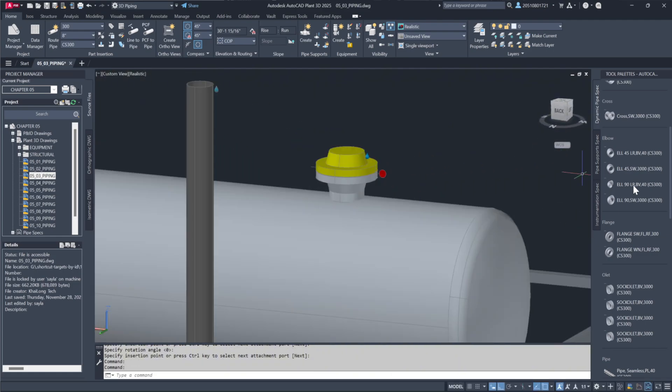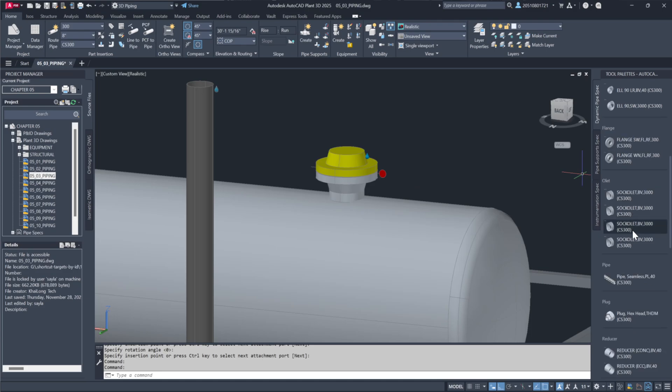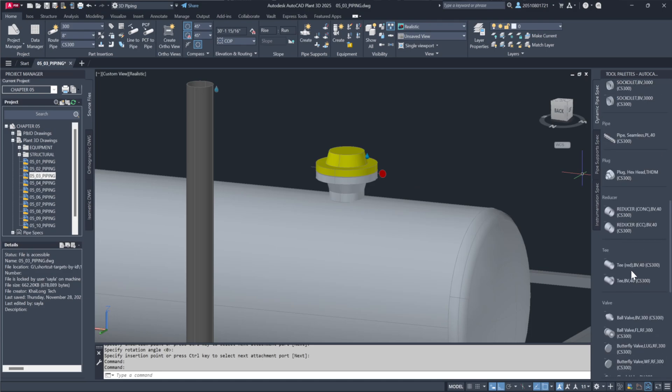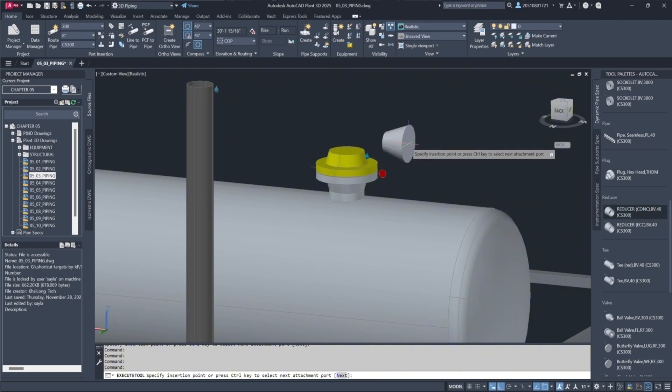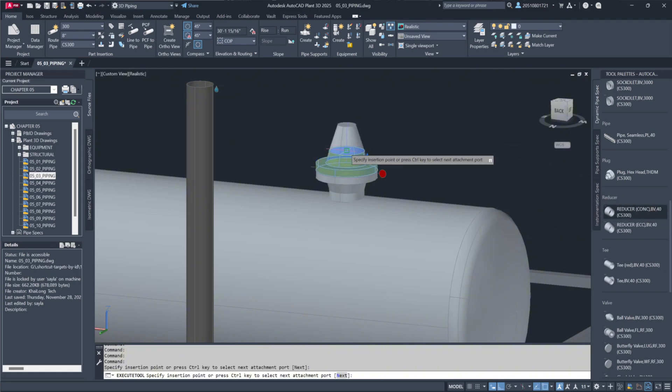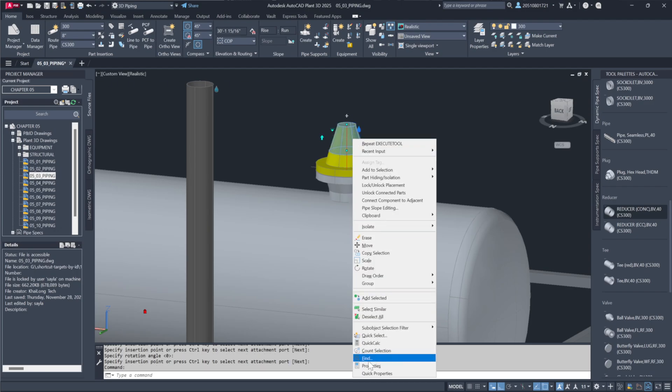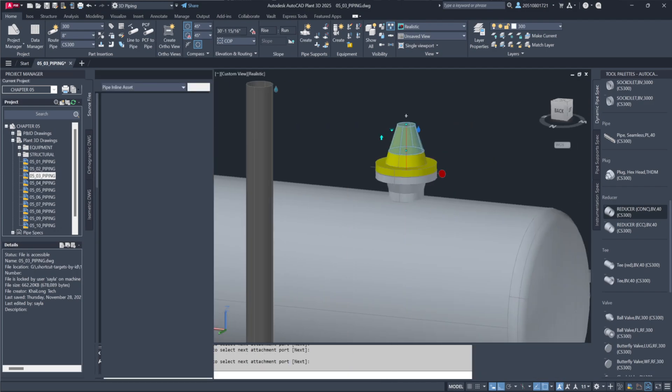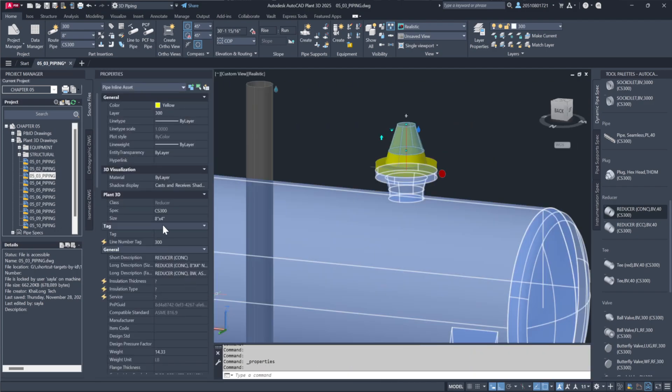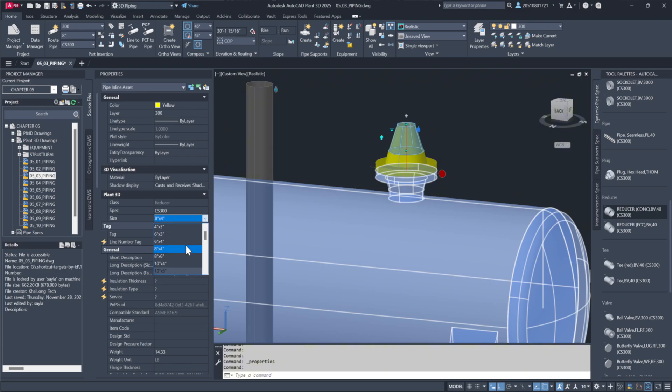Now, to connect to this line, I'll use a reducer since we need to reduce from 8-inches to 6-inches for the existing pipe. I'll manually place a concentric reducer by selecting it from the fittings. I'll position it until it snaps to the node. Let's confirm it's an 8-by-6 reducer by checking the Properties tab.